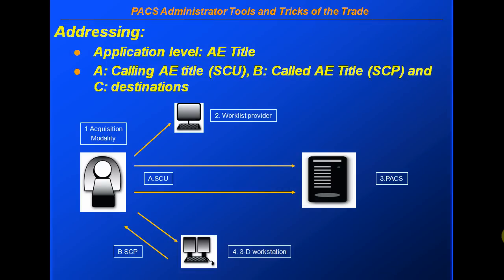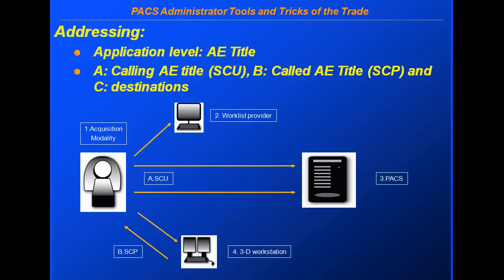Let's first talk about addressing at the application level. A device has an AE title — Application Entity title — and the AE title assigned to a modality is always unique. There is a Calling AE title, which is the service class user. That is the AE title used when a modality or any other device opens a DICOM association.